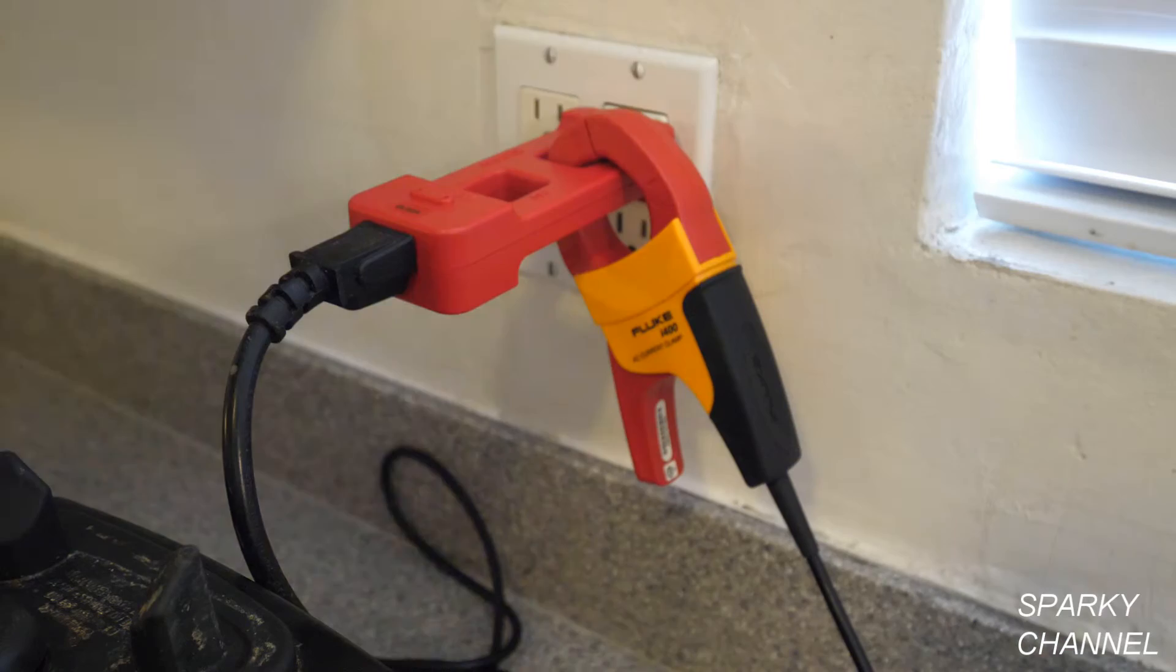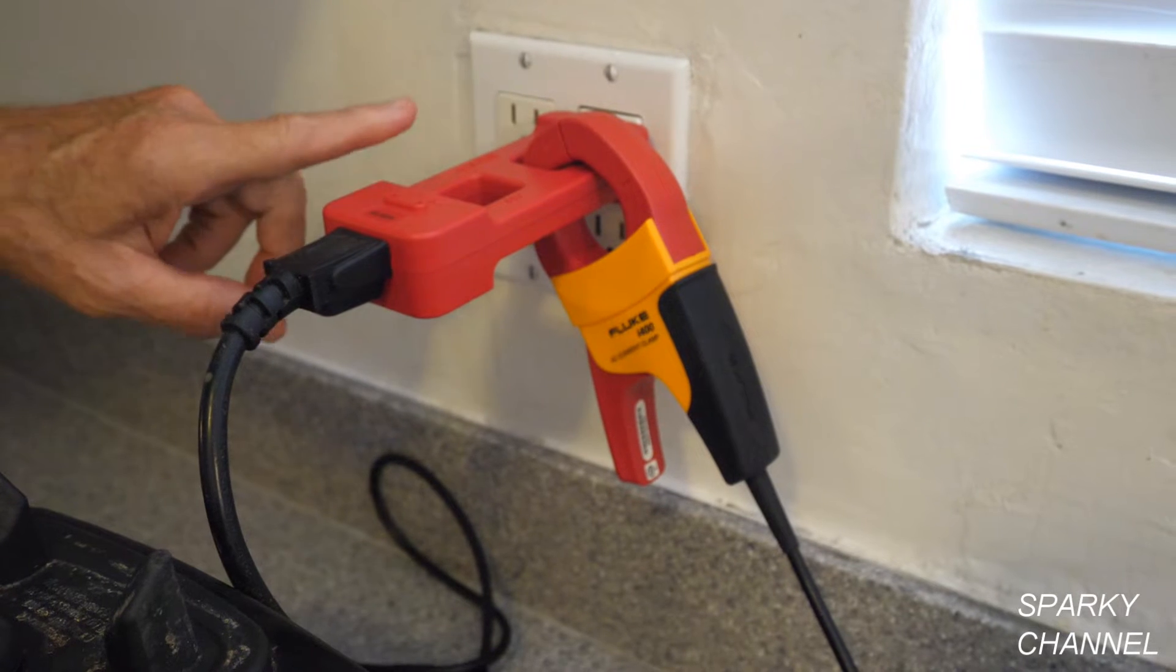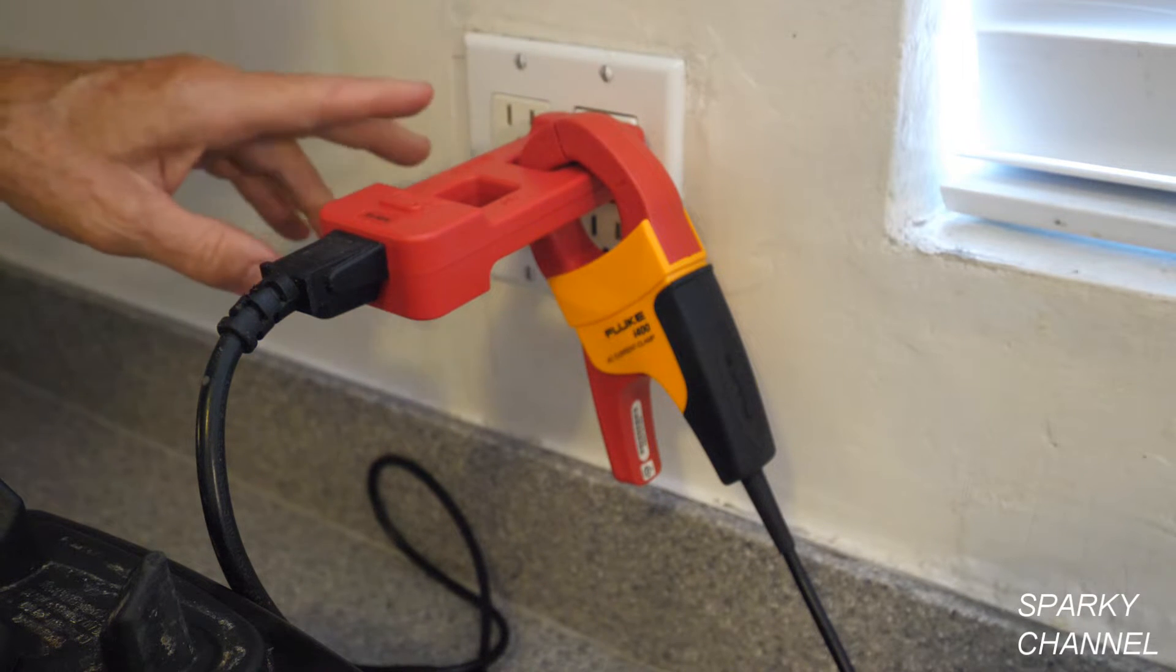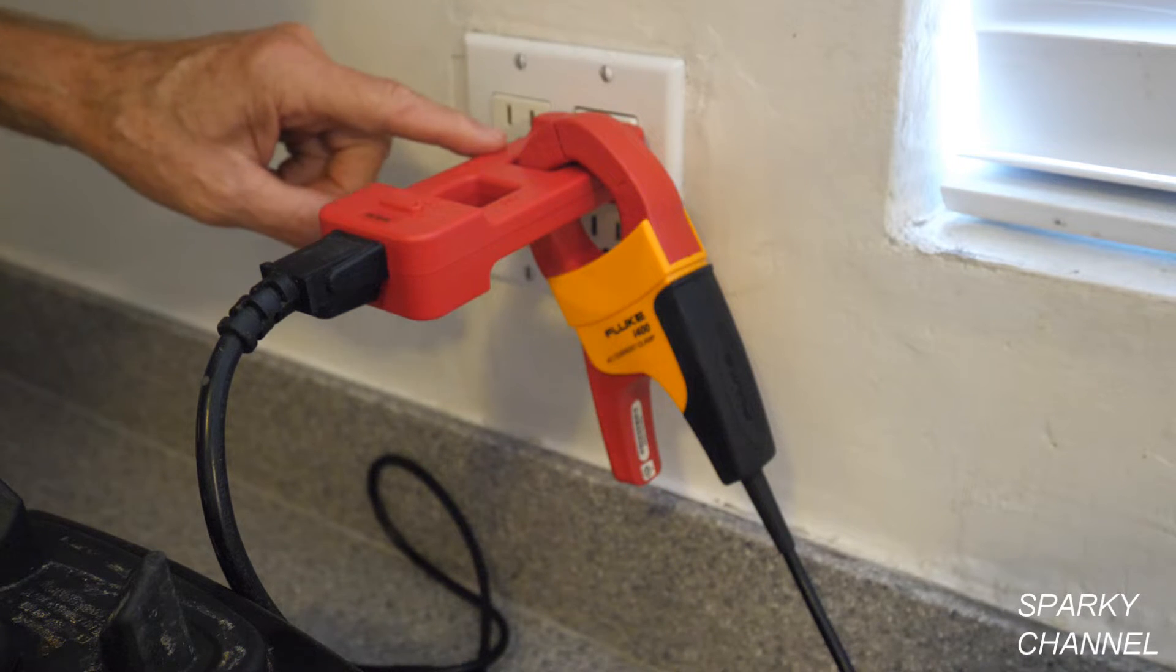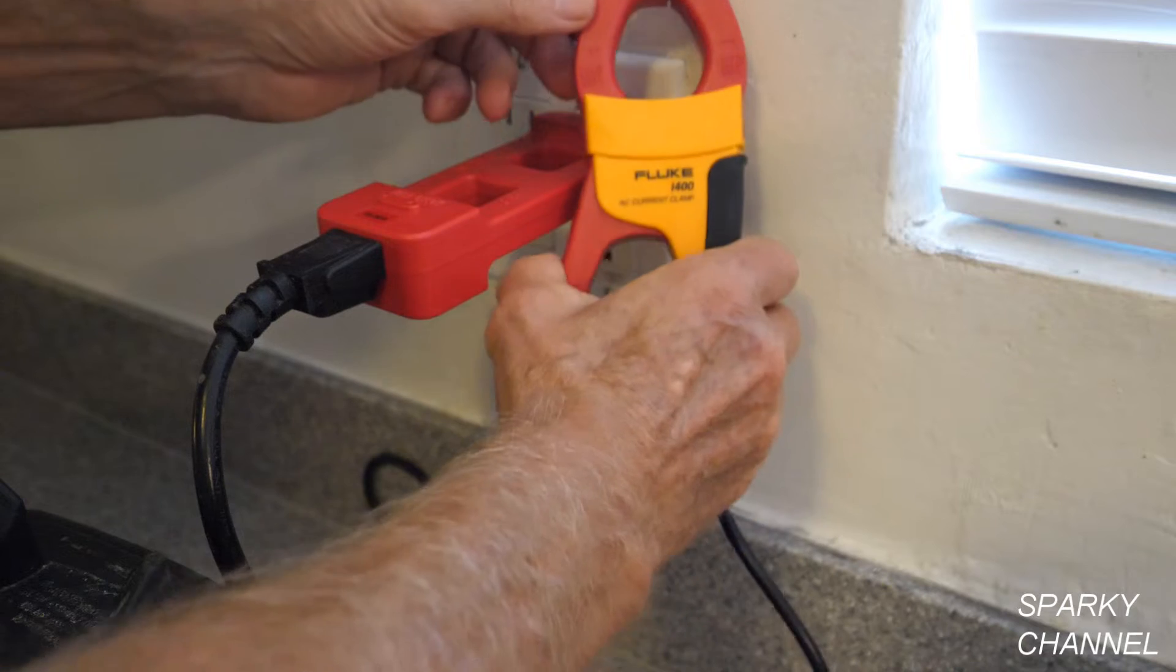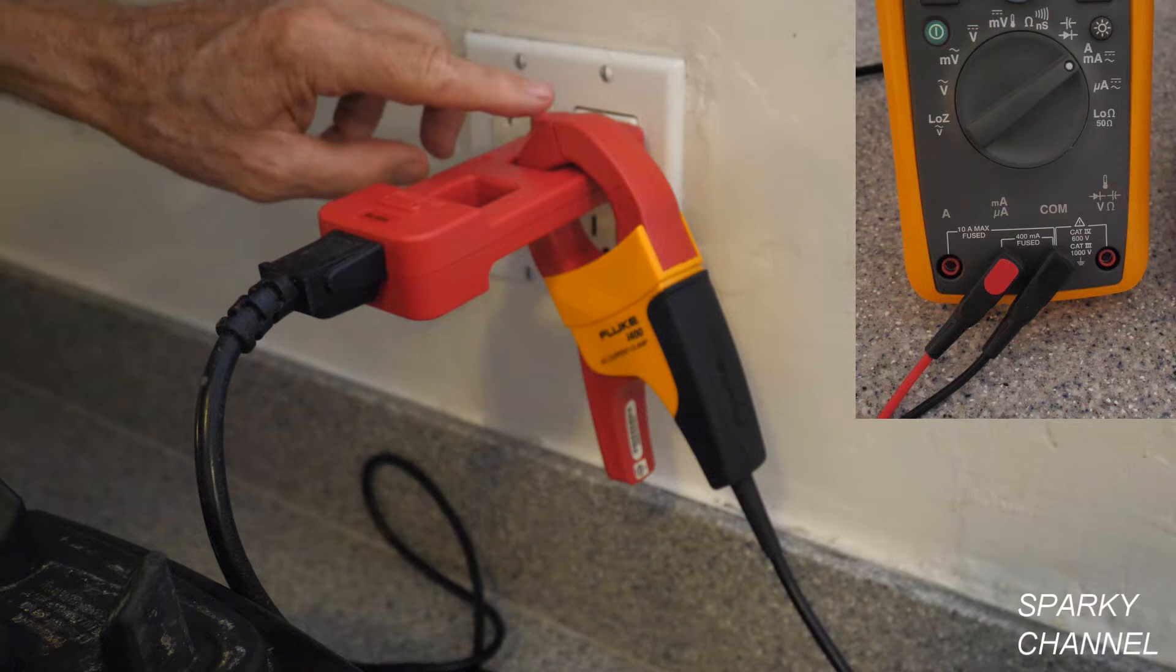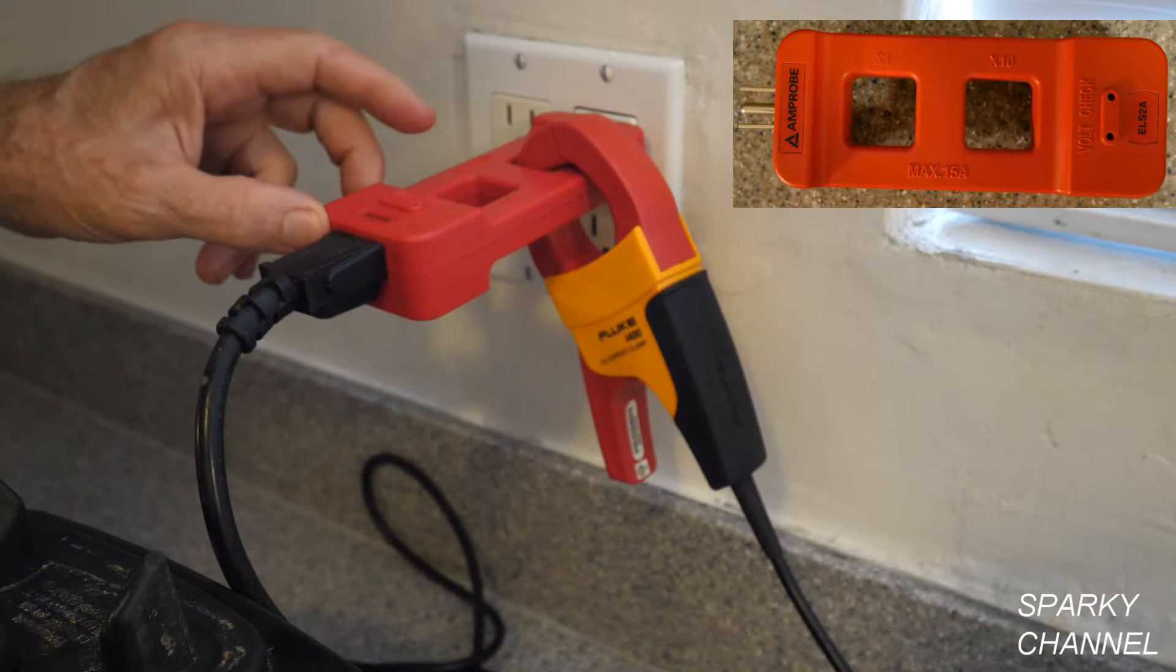This receptacle is part of a 20 amp circuit. I have an AC line splitter plugged into the receptacle. And what this does, the current comes out from the receptacle and flows through these sides of the AC line splitter. And it splits the current to a hot side and a neutral side. Therefore you can put a clamp meter or in this case I have a Fluke I400 AC current clamp that goes to the 289. I'll show you the connection there in just a moment. But you can put a clamp meter or a current clamp into one of these two slots of the AC line splitter.